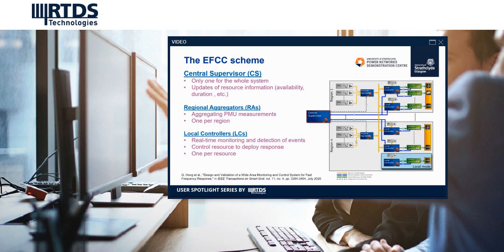Combining these two sets of information, you will be able to detect the event and understand how much it should contribute to respond to that event. So for the whole process, we are aiming for a response control signal to be sent within 500 milliseconds and to deliver a response within 1 second. Because of the limited time, I'm not going to go into the detailed algorithm behind each block here. So for those who are interested, please refer to our paper as listed at the bottom of the slide.